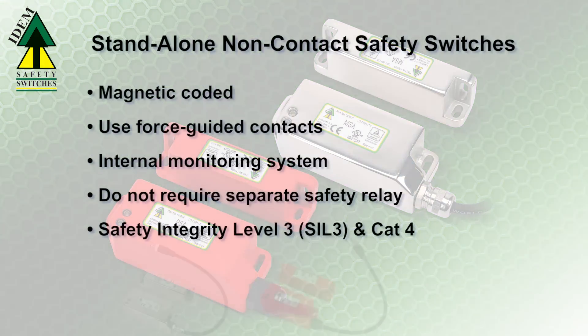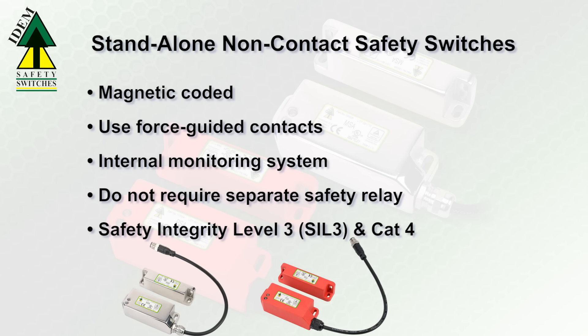New IDEM non-contact magnetic coded switches use force-guided contacts and have an internal monitoring system so that they are stand-alone, not requiring the use of a separate safety relay.